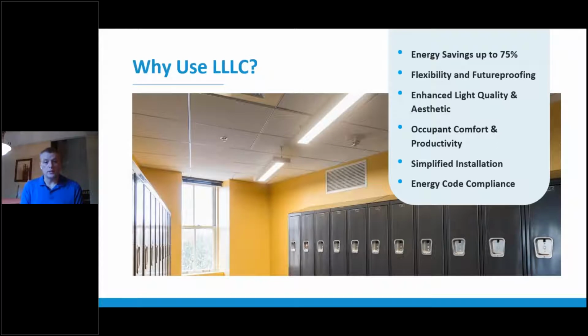So why LLLC? What we found, and the study will show a bunch of this, is that we see energy savings, pretty substantial energy savings, depending on the building type and use case, up to 75% energy savings from the controls. We see flexibility and future-proofing with the systems, because every fixture has a sensor in it, and every fixture is controllable down to an end node of that fixture, but not necessarily giving individual control to the person. You have the flexibility to create bigger zones or bigger groups or scenes, and it just allows for changes in the future without big expense.